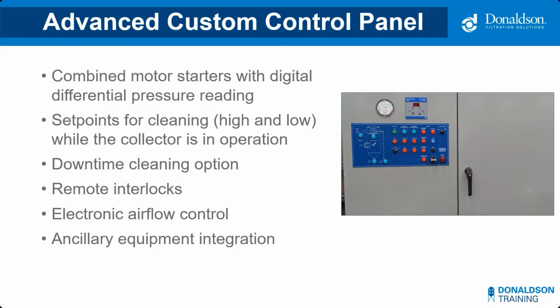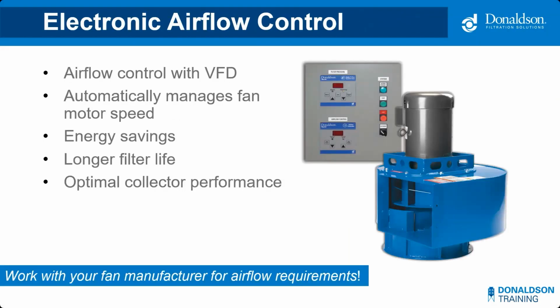An advanced control panel typically uses electronic airflow control instead of manual airflow control. And I want to dig into that just a little bit more. Previously, we discussed how you could control the airflow through dampers and slide gates, which is just a lever that you would pull to adjust the amount of obstruction in the airstream. But you can also manage airflow electronically by the use of a variable frequency drive, also called a VFD, along with an airflow controller.